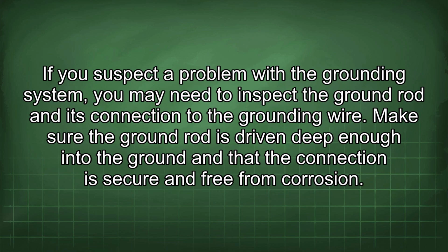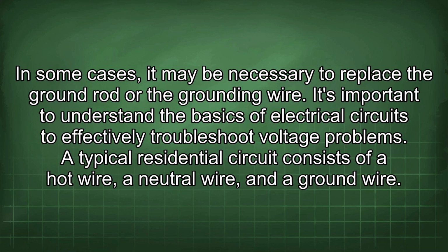If you suspect a problem with the grounding system, you may need to inspect the ground rod and its connection to the grounding wire. Make sure the ground rod is driven deep enough into the ground and that the connection is secure and free from corrosion. In some cases, it may be necessary to replace the ground rod or the grounding wire. It's important to understand the basics of electrical circuits to effectively troubleshoot voltage problems.